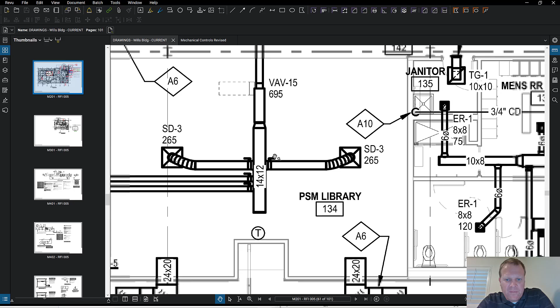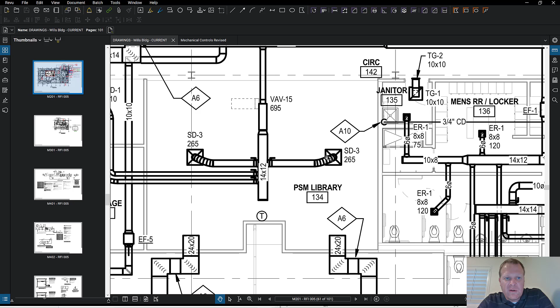How do they actually make sure that you get 265 cubic feet of air per minute? One, they put a hood underneath this, and it needs to be a finished space with the ceiling in and the doors on usually, so it looks finished and everything's running. Then, do you see this little thing right here? That's a damper, a manual damper, and they'll be able to manually open and close this to allow more or less air into the duct so they can read that they're getting 265 cubic feet per minute.